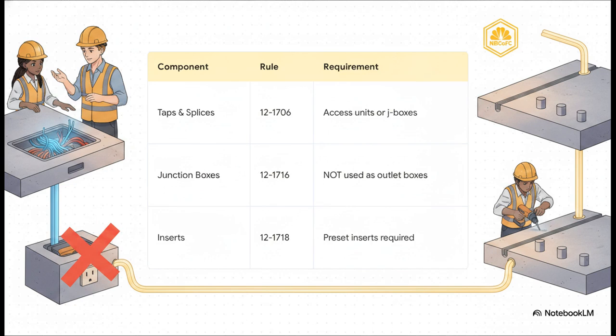Furthermore, if you happen to be working with post-stressed or pre-stressed concrete floors, Rule 12-1718 says you have to use preset inserts. If you realize later you need to drill an after-set insert, well, it's got to comply with the National Building Code of Canada. Why? Because drilling into a stressed slab risks compromising the entire structural integrity of the floor, and yeah, that's a really bad day.